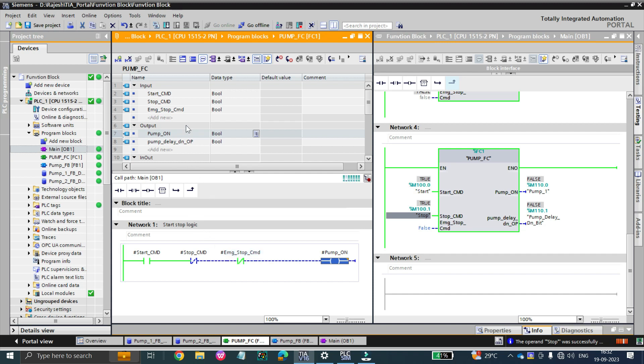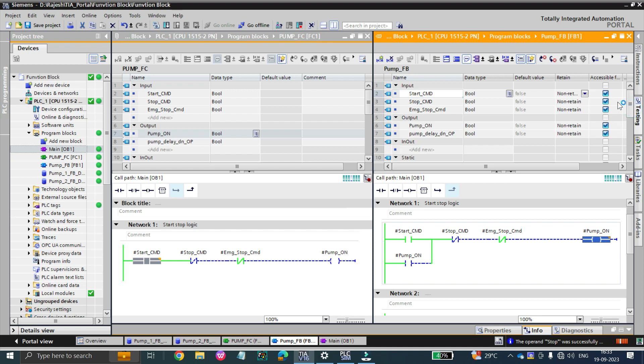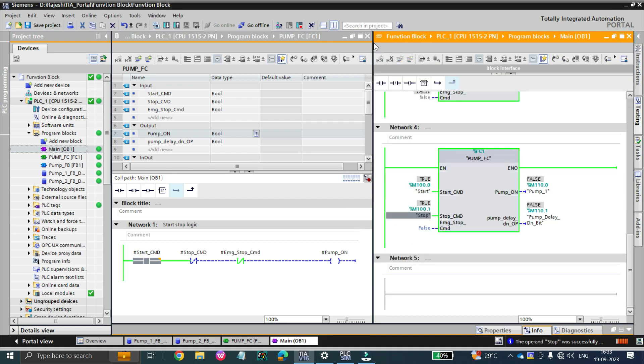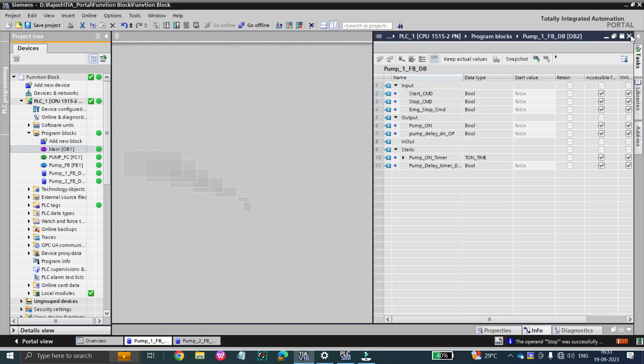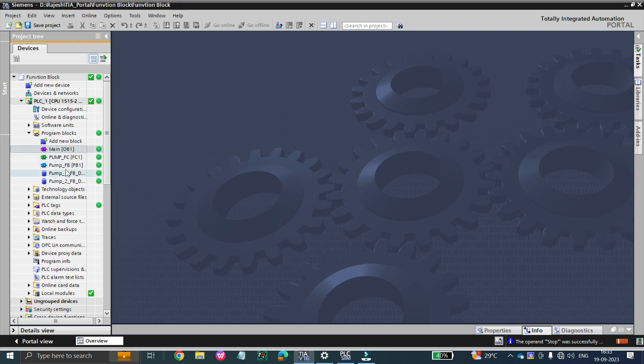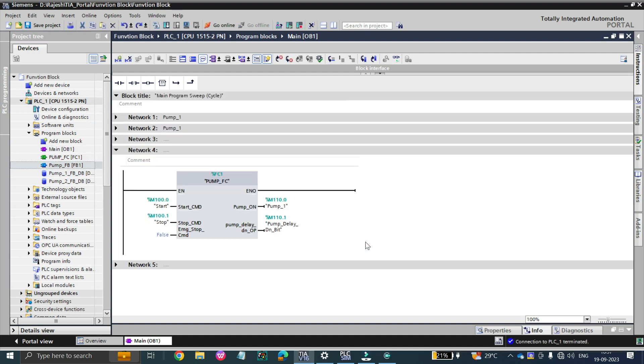So what happens if you use a function with its local tags? You can't do much, while in a function block you can do a lot — you have tons of tags that can be stored in internal memory bits like the static tag. Now you might ask: if function has those disadvantages, why use it at all? The reason is that every time you call a function, no DB is created. So if you use a function block, you should use it only when you have multiple instances that need their own memory.